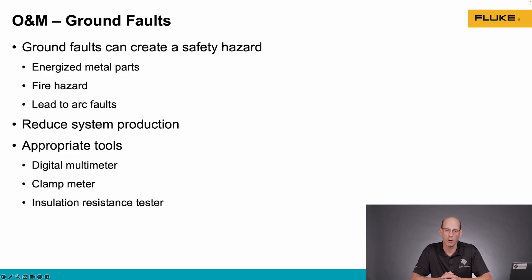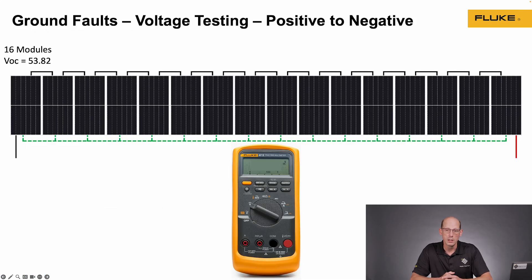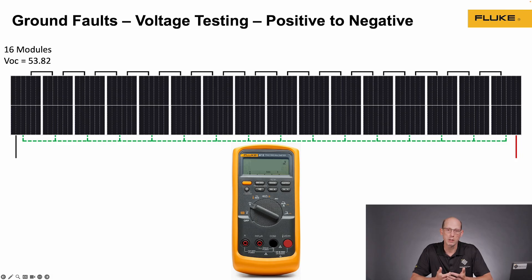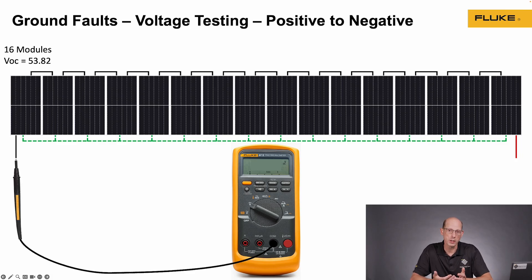We can use different tools to find ground faults. Multimeters and clamp meters are a good option, and also insulation resistance testers to find circuits with low resistance to ground. Here's an example of finding a ground fault using voltage. We have a string of 16 modules wired in series — approximately 53 volts per module. When I measure between the positive and the negative of this string, I should get approximately 861 volts.